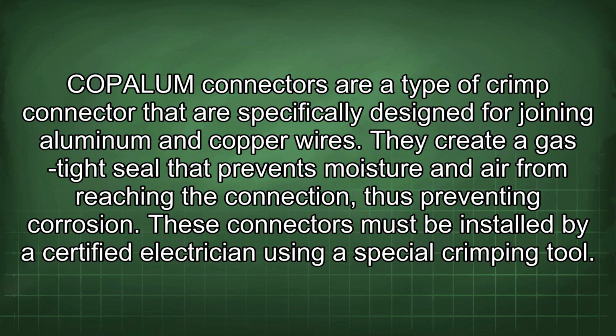COPALUM connectors are a type of crimp connector that are specifically designed for joining aluminum and copper wires. They create a gas-tight seal that prevents moisture and air from reaching the connection, thus preventing corrosion. These connectors must be installed by a certified electrician using a special crimping tool.